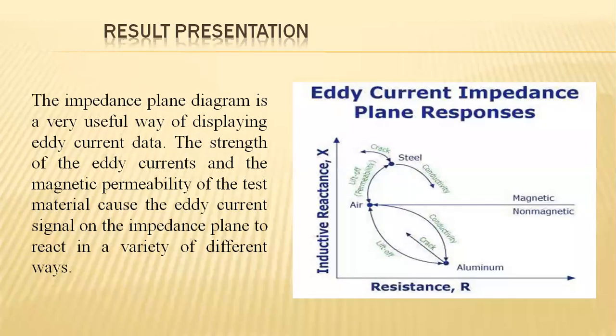Which materials will come under the magnetic field excitation sources? Here we have a clear-cut representation. The magnetic field will vary only for the ferrous content materials such as steels and combinations of steels or compositions of ferrous materials, with lift-off, permeability, maximum generation of permeability, and conductivity taking place.